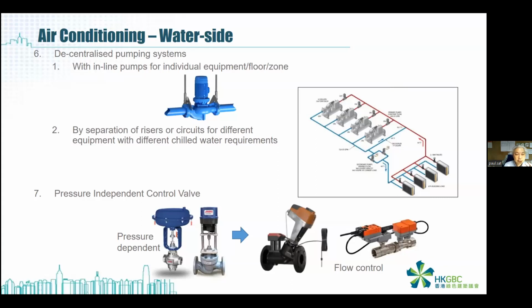The second one is that we can divide large scale systems, the circuits, into different sub-circuits, and we can use different variable speed pumps at different capacities to treat each system. So that different systems, no matter whether the scale is large or small, can have their own pressure requirement. We do not confuse it, so that they can optimize the pressure head requirements for each circuit.